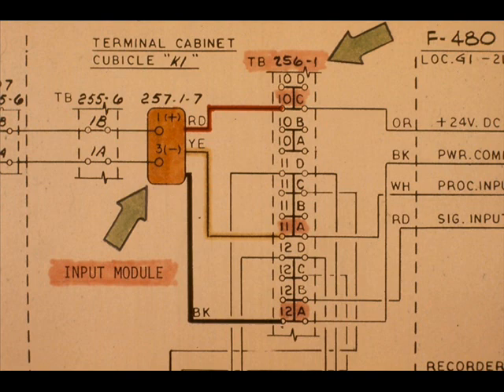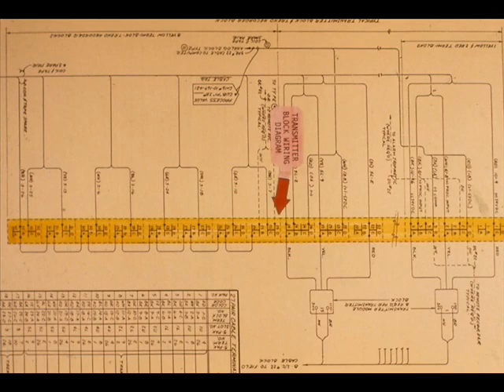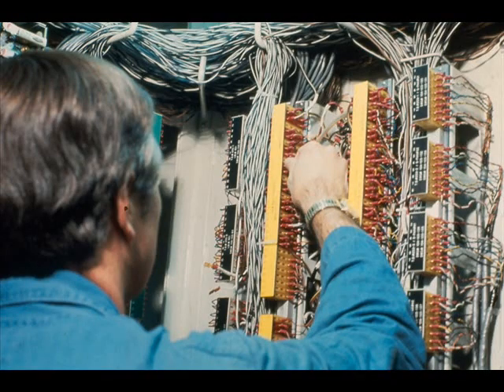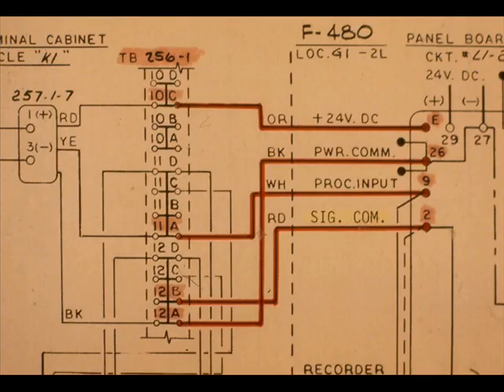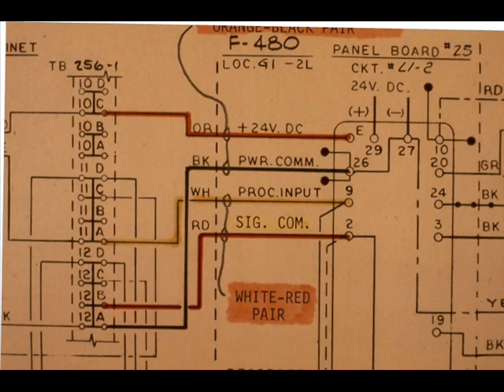The input module wires terminate on TB256-1, as shown on the loop diagram, or as shown on the transmitter block with module wiring diagram. Terminate the input module wires. The next portion of wiring we will terminate will be that wiring which connects TB256-1, the transmitter block, to the controller. This will complete the input wiring. This circuit consists of 2-wire pair in a multi-pair cable. One pair is orange-black. The other is white-red.